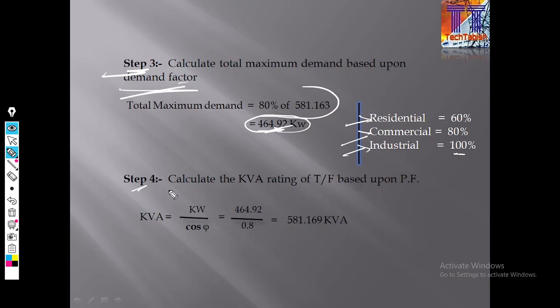Now the step 4 is calculate the kVA rating of transformer based upon the power factor. We all know transformer is calculated in kVA, not in kilowatt. Why? Because of two reasons. If we talk about the reason, so reason first, what is the reason first?